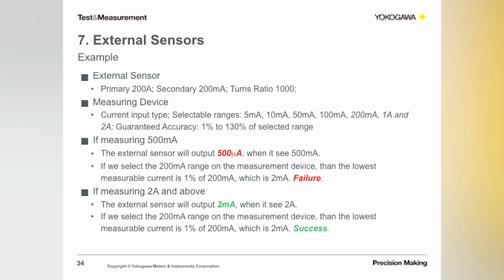But now if you're expecting to measure 2 amps using that external sensor, the sensor will output 2 milliamps, which is within the guaranteed measurement range, and this scenario will result in success. Basically, it will be a guaranteed accuracy that you're measuring 2 amps, right? I mean, our application engineers get many calls that are related to this mismatching. So, be careful, be prudent, when selecting external sensors. Make sure they're properly matched with your measurement device.